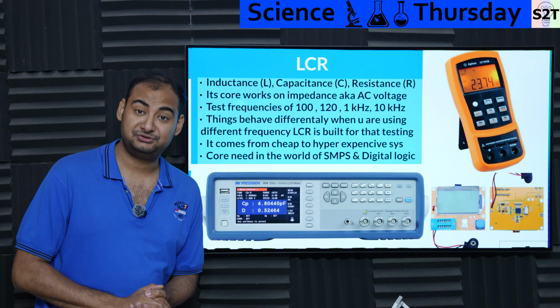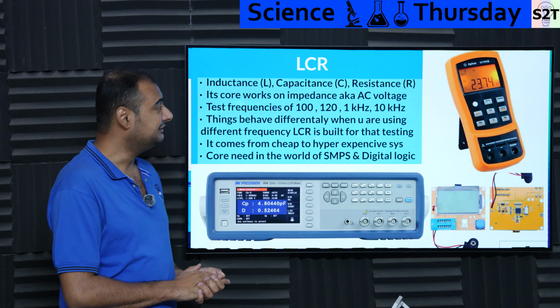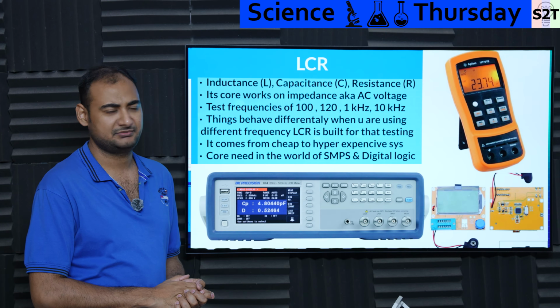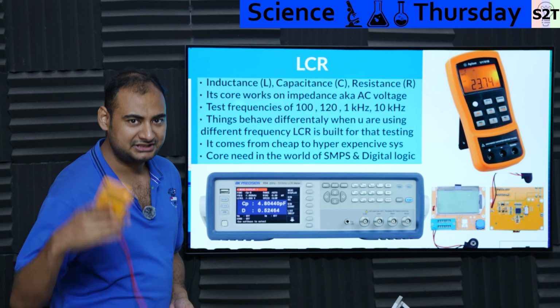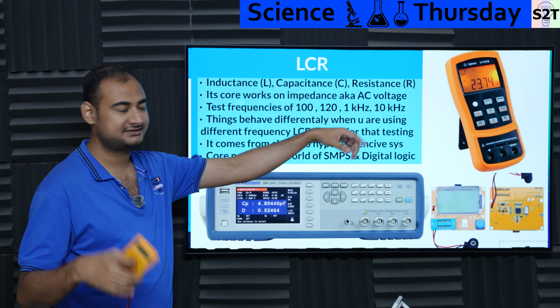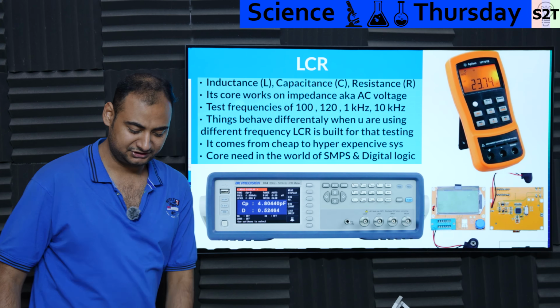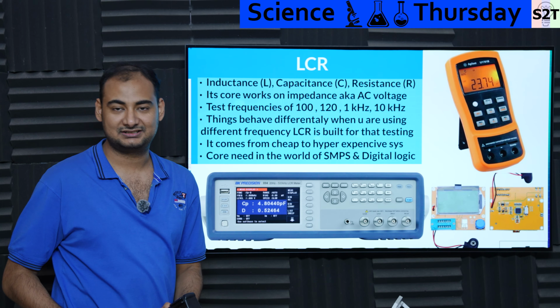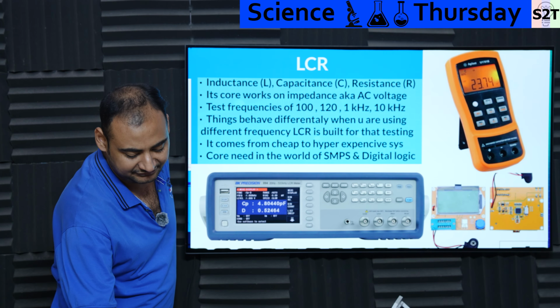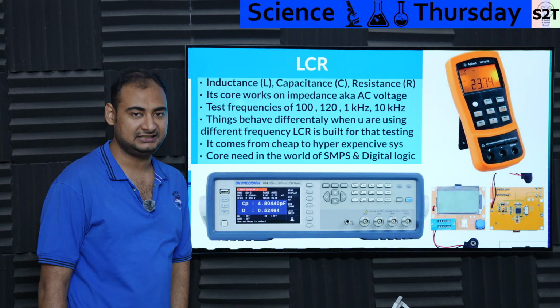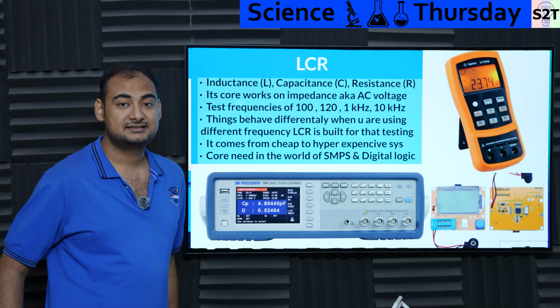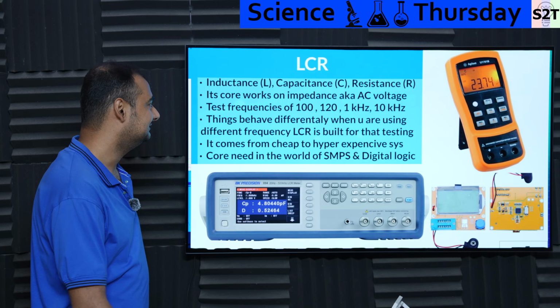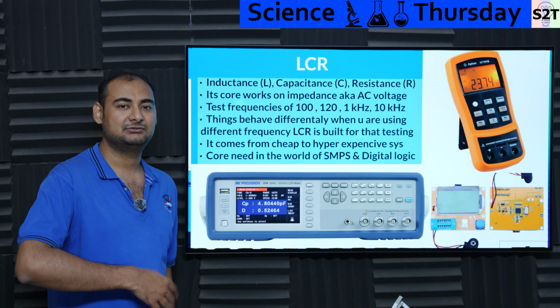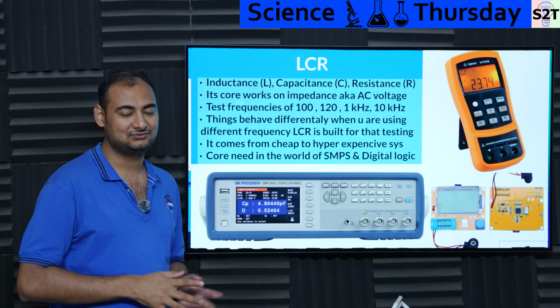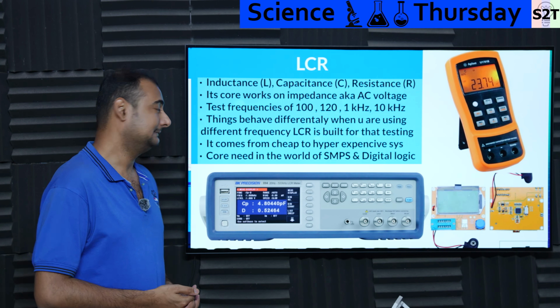Now we come to another unique puppy, which is LCR: inductance, capacitance and resistance. Wait a minute, isn't it that all multimeters can handle resistance, even high resistance, and capacitance? Some of the new ones have capacitance. So what's the deal here? Well, high frequency makes these things behave differently, meaning you go from resistance to impedance, and that's the whole point. They have to work with not DC, not high voltage, not low voltage, but an AC frequency signal.